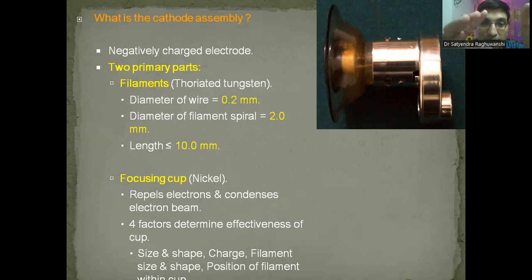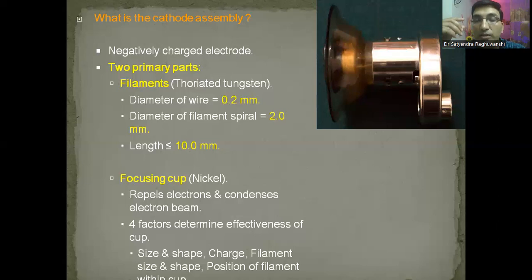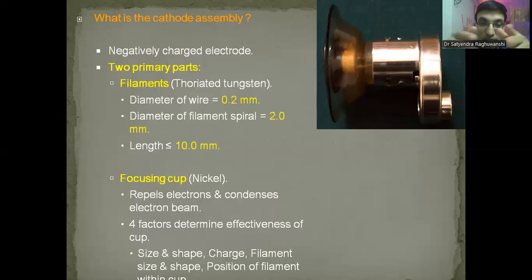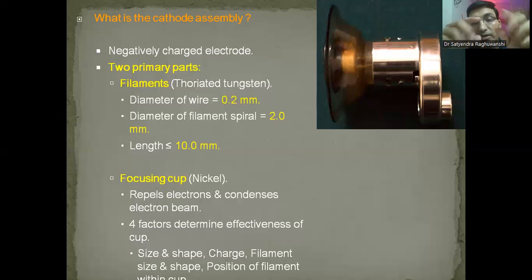What is the purpose of the focusing cup? During thermionic emission, there is an electron cloud all around. When electrons leave the filament they might go anywhere, but we need a focusing cup to target them onto the tungsten-rhenium target track. We don't want the electron beam to go haywire — we want it to reach the target track. So we have a nickel focusing cup. What is dual filament? Modern x-ray tubes have dual filament. The larger filament has a larger focal spot, used for larger body parts with lower resolution. The smaller filament provides better resolution and is used for smaller body parts.